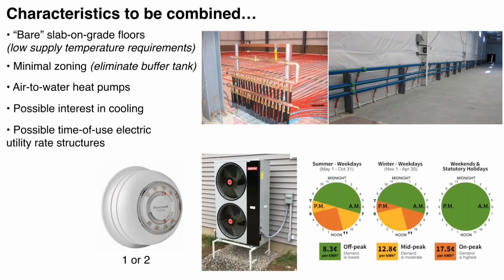And another really nice feature or benefit of this approach is in areas that have time of use electric rates. And I just put down there in the lower right an example of time of use rates. And you can see during the evening and the overnight hours, in this case, the rate was 8.3 cents per kilowatt hour. During the peak demand period there in yellow, it jumped up to almost 13 cents a kilowatt hour. So how could we coordinate the operation of the heat pump with the high thermal storage ability of the slab and with these rate structures?